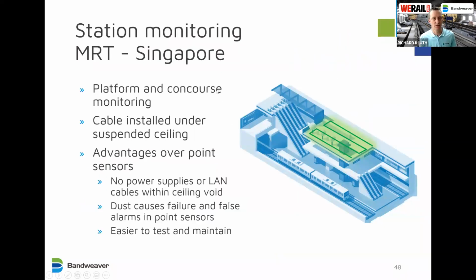Moving on to station monitoring. So for the mass rail transport in Singapore, they monitored platforms and concourses using this technology. They installed the system in the suspended ceiling, in the ceiling void. And just worth emphasizing, they also monitored the tunnels, but once they understood the benefits and versatility, they used it quite extensively through the nation. And the reason they did this over using conventional point sensors is they found that there's no power supplies or LAN comms cable needed within the ceiling void. With point sensors or beam detectors, dust can cause failure and false alarms, so it's not susceptible to that. And it's also easier to test and maintain. You don't need to get into the ceiling void to repair the cables.